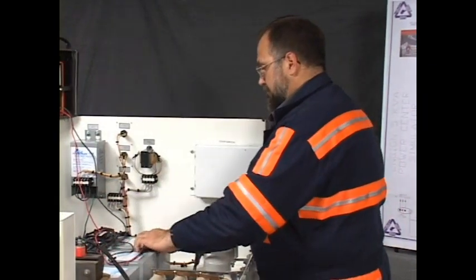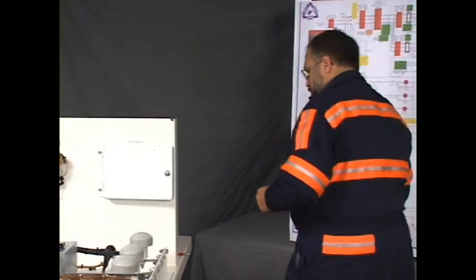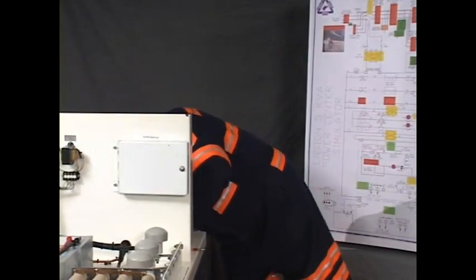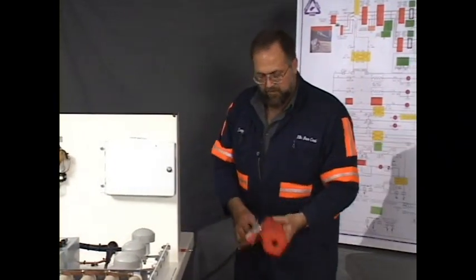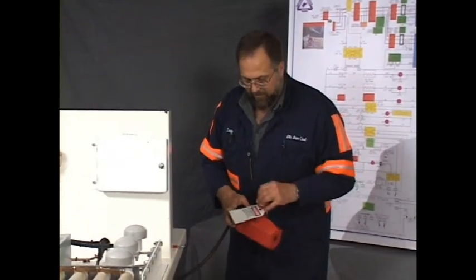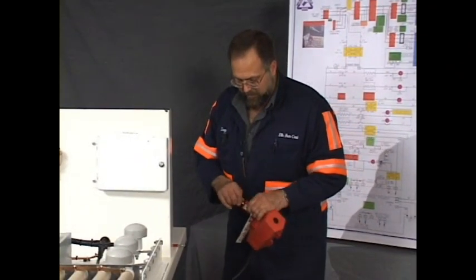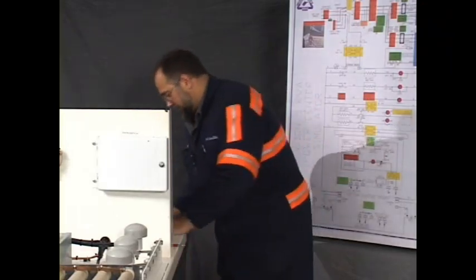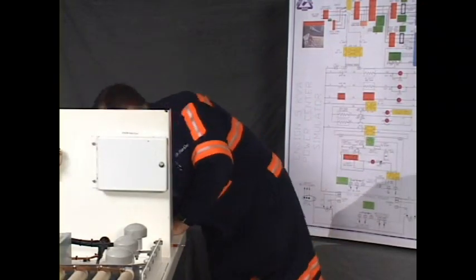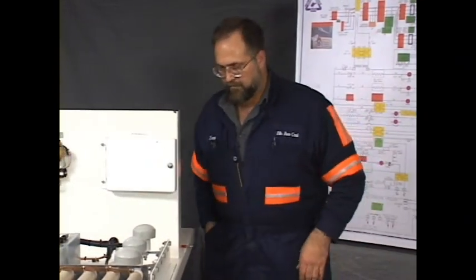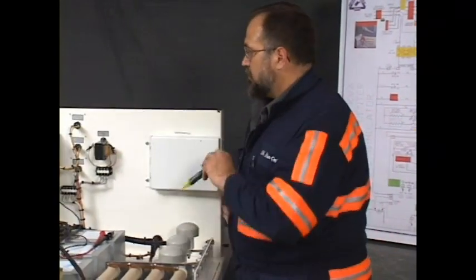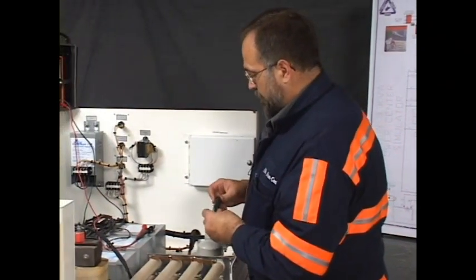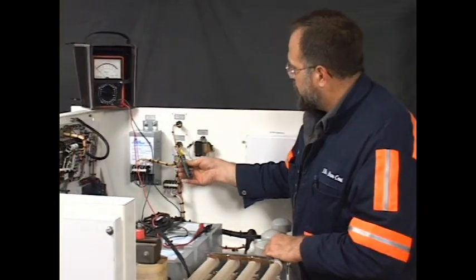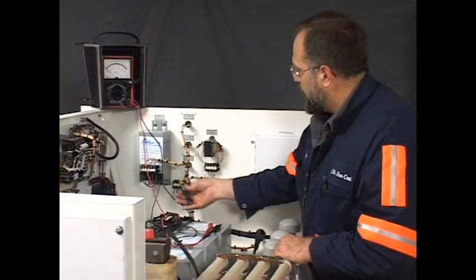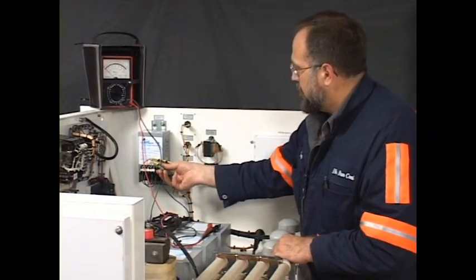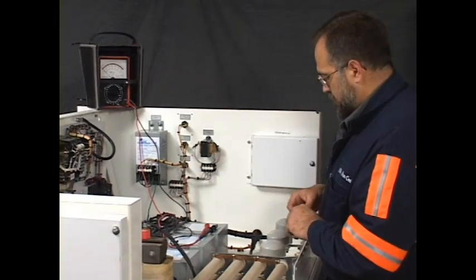Gives you good information. I'm going to make sure that our circuit is disconnected, locked and tagged. This is the power supply cord. As you can see, we have a lock and a tag on it. Now I'm going to take the key with me. I'll take a voltage test before I begin my troubleshooting to be sure that I have no power on any of the incoming lines. And I do not. There's no power.